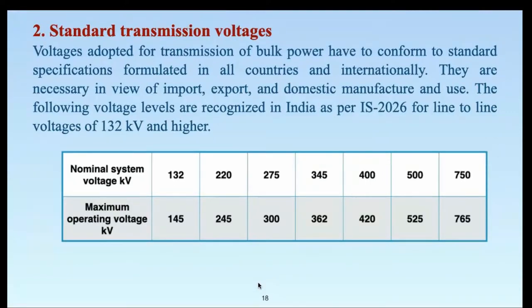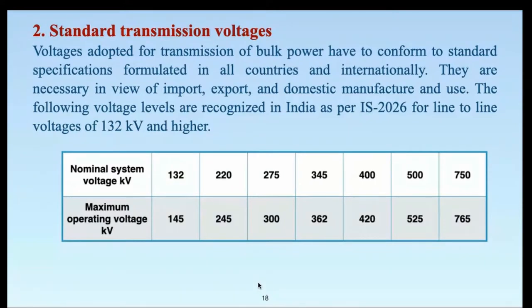The power handling capacity mainly depends upon two or three important parameters: one is the transmission voltage, second is the positive sequence reactance and series compensation, and third is the transmission distance. Among those parameters, the most vital parameter with the highest impact on power handling capacity is the transmission voltage — the standard transmission voltages.